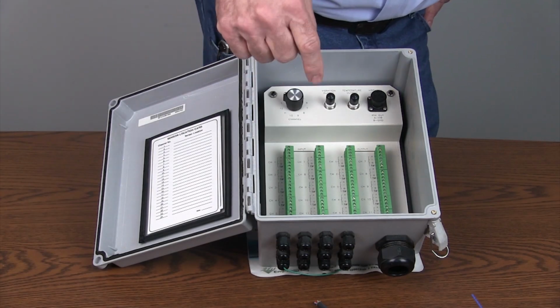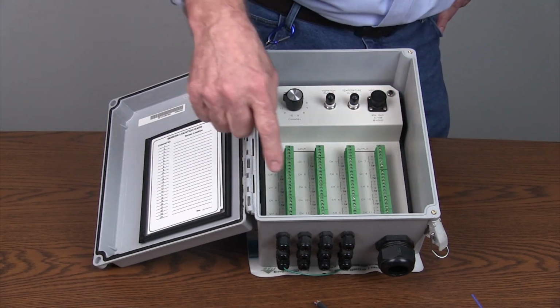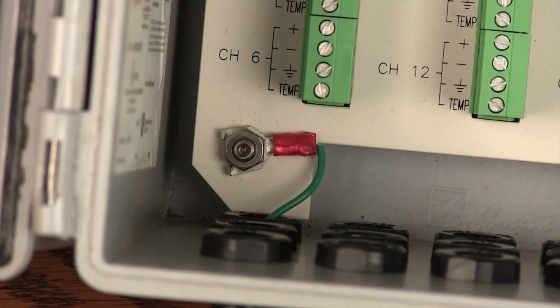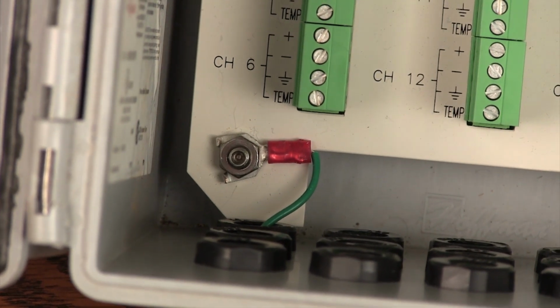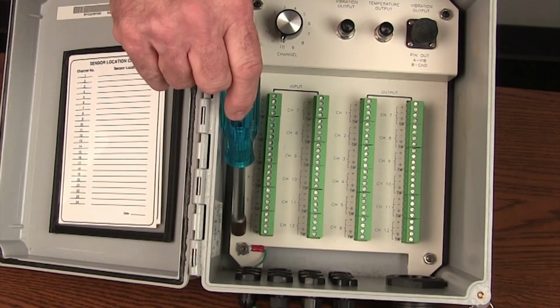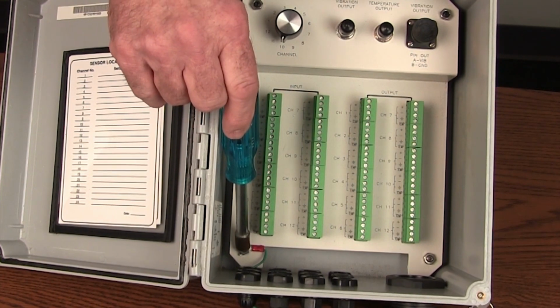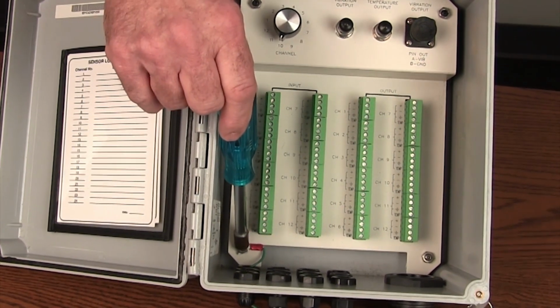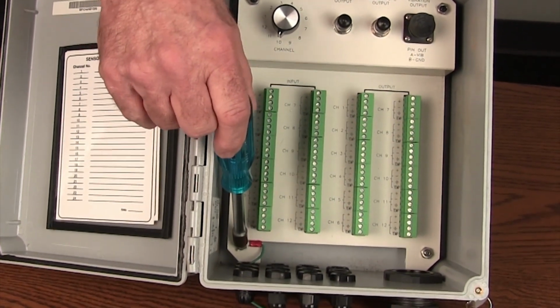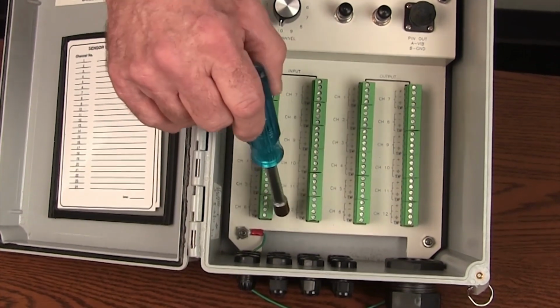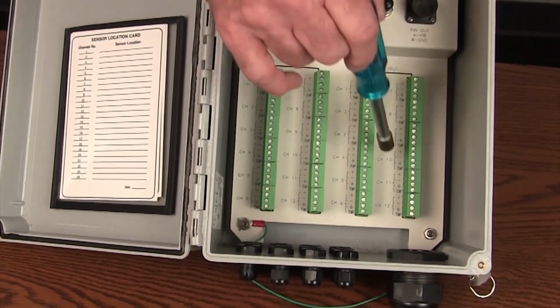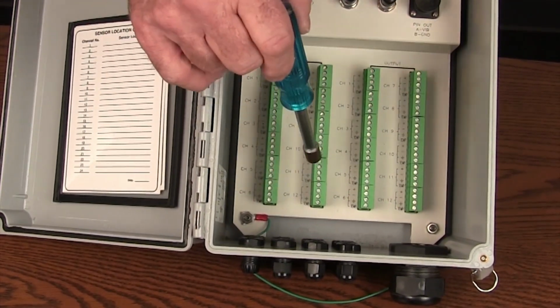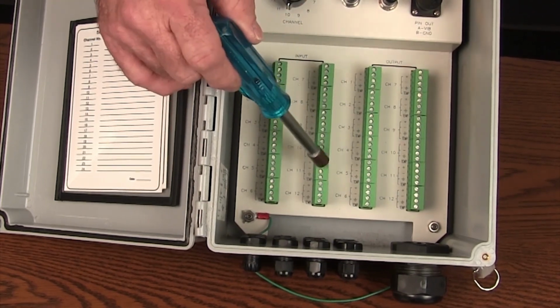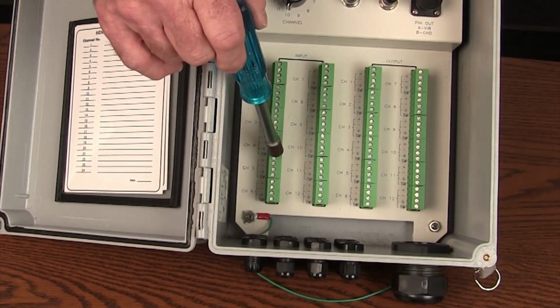Every IMI sensor's termination box has a grounding lug at the bottom left-hand corner. The grounding lug is wired to shield on the back plane of each terminal strip. Therefore, all of the accelerometer shields are connected to the grounding lug, which should be connected to earth ground during the installation. This prevents noise from affecting the vibration measurement, which can lead to artificially high vibration levels and ski slope in the FFT.